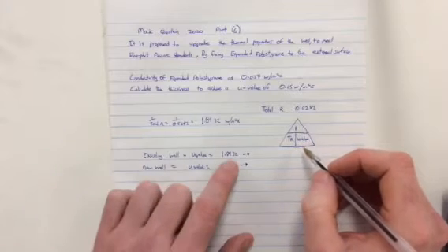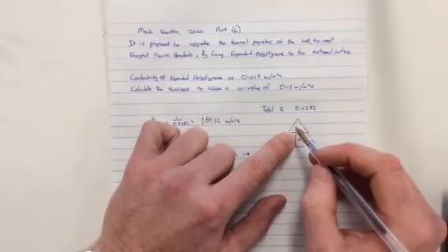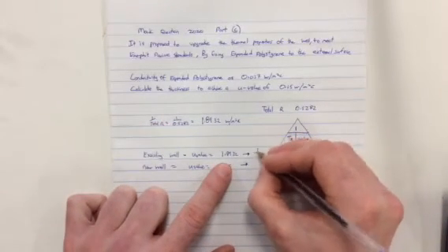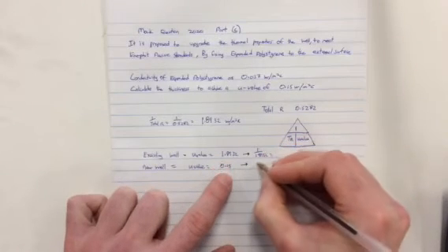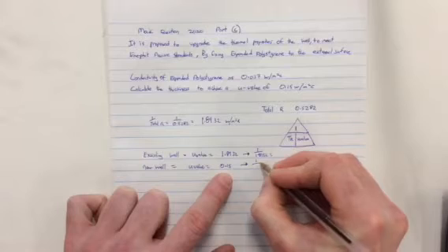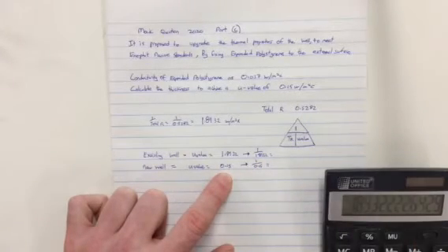look at what we have. We have the U value and we have the number 1. If I'm trying to find total resistance, put my finger over that, I have to divide 1 by the U value, and that's going to get me my resistance figure. So 1 divided by the U value. Here 1 divided by 1.8932 equals whatever, and then 1 over 0.15 equals whatever. We'll do that calculation now.